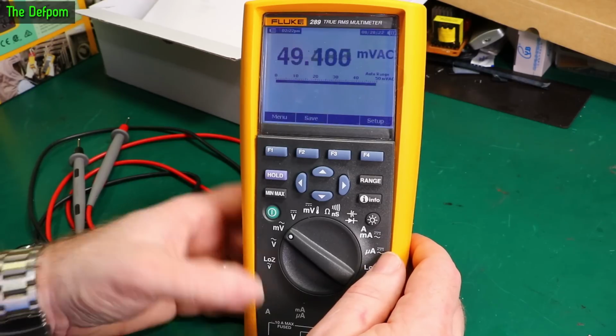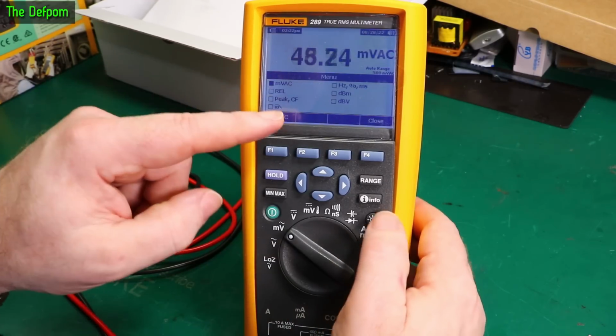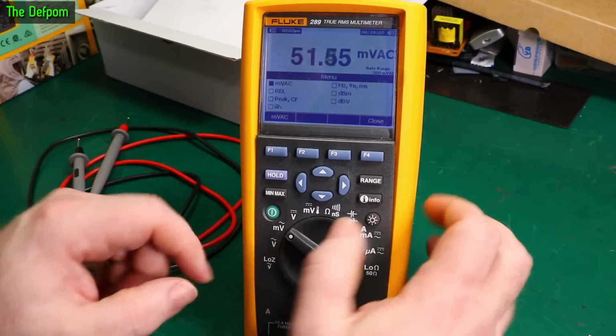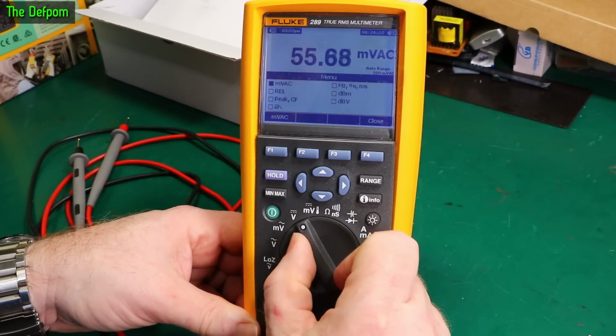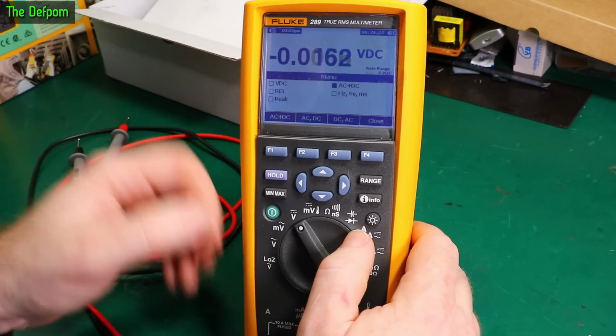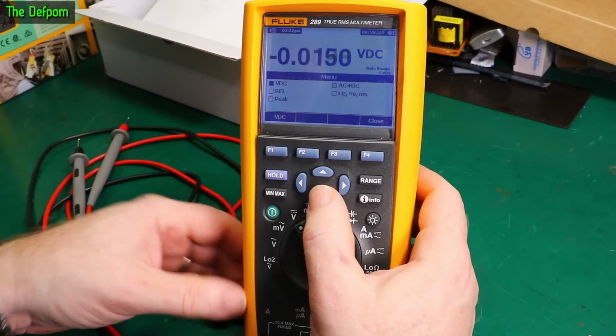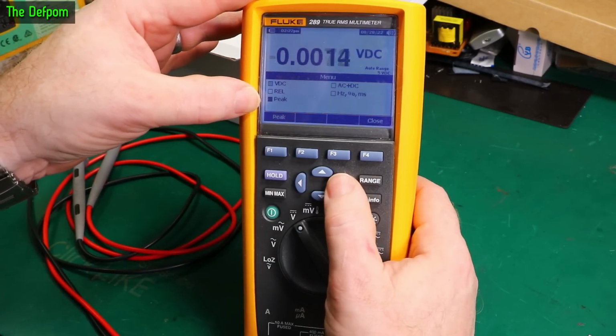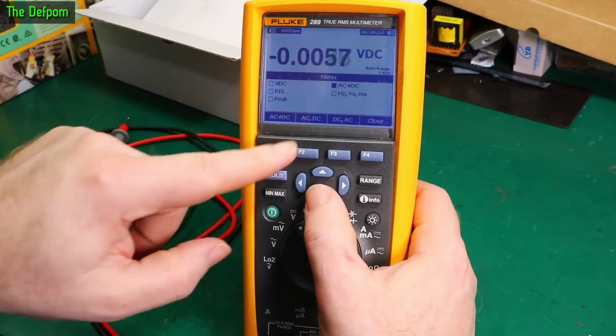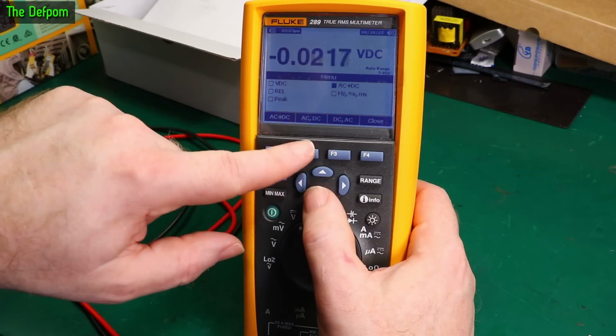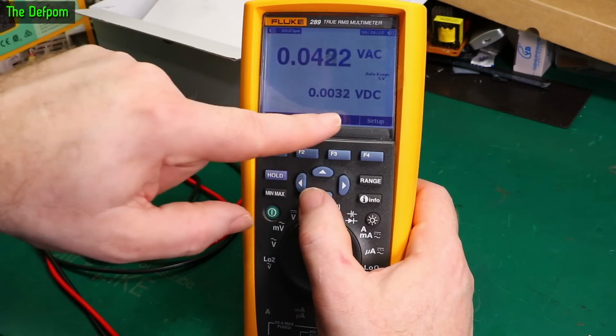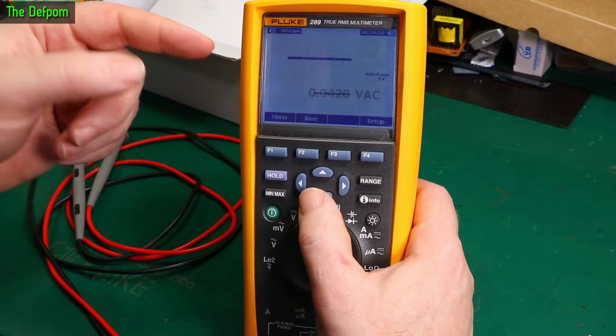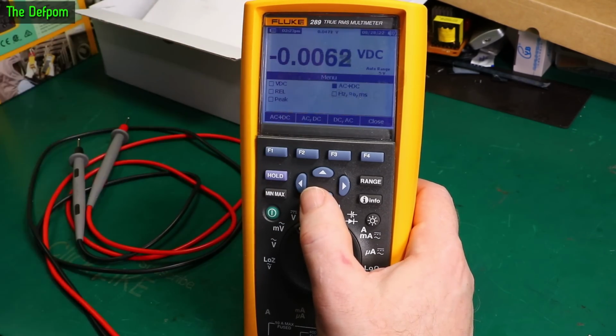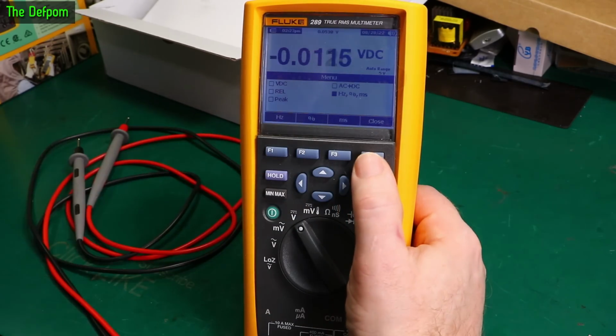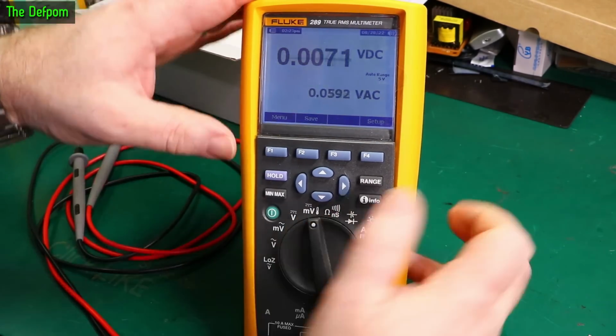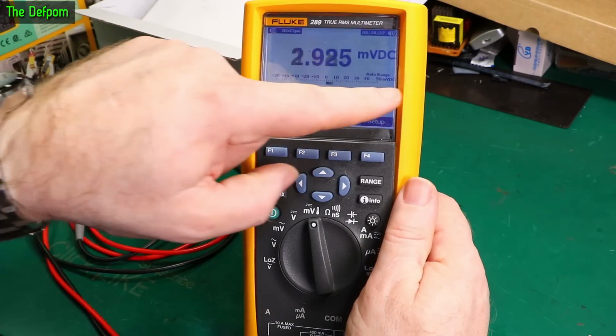So in millivolts, we've got millivolts AC, hertz and stuff, same as the volts range - this is the AC section. Volts DC, like I said before, we've got different options: plain volts DC, relative mode, peak mode, AC plus DC options, so you can do AC and DC, AC primary DC secondary, or the other way around which I showed before, DC then AC - whichever way you want as your main display. You've also got other options over here. And millivolts, I imagine that's probably the same options. It's got the bar graph across here as well.